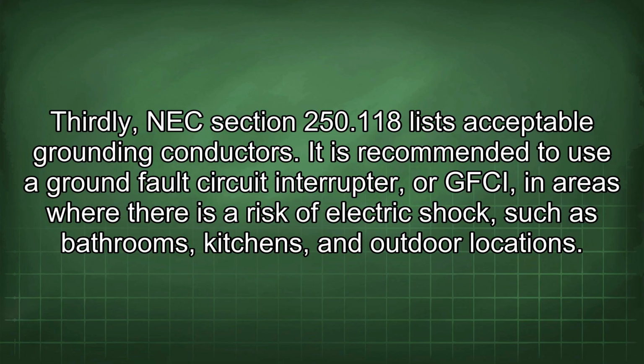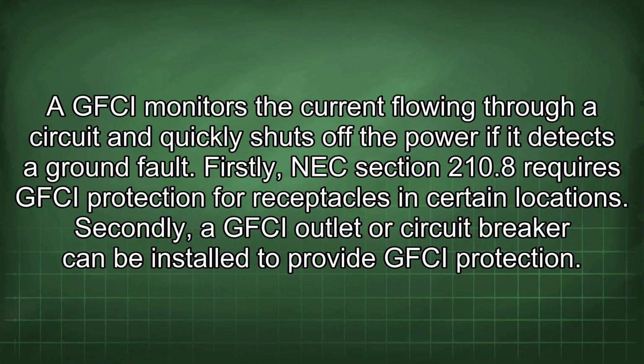It is recommended to use a ground fault circuit interrupter, or GFCI, in areas where there is a risk of electric shock, such as bathrooms, kitchens, and outdoor locations. A GFCI monitors the current flowing through a circuit and quickly shuts off the power if it detects a ground fault. Firstly, NEC Section 210.8 requires GFCI protection for receptacles in certain locations.